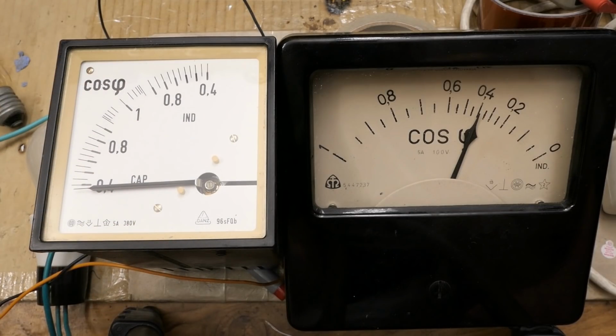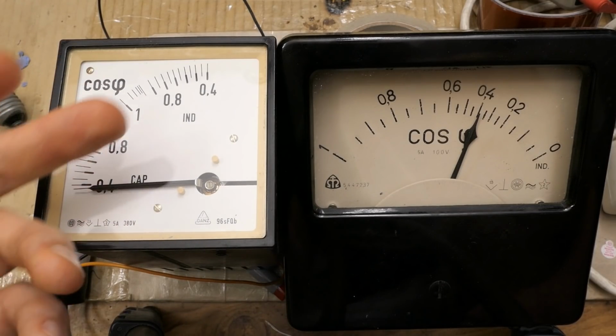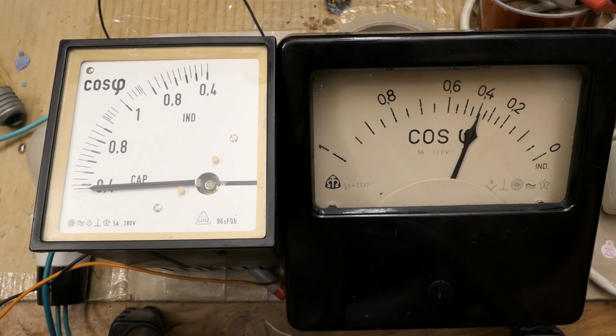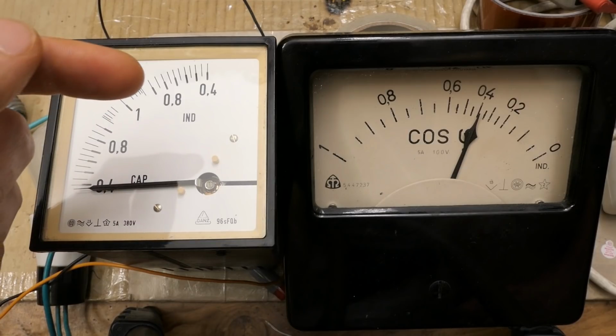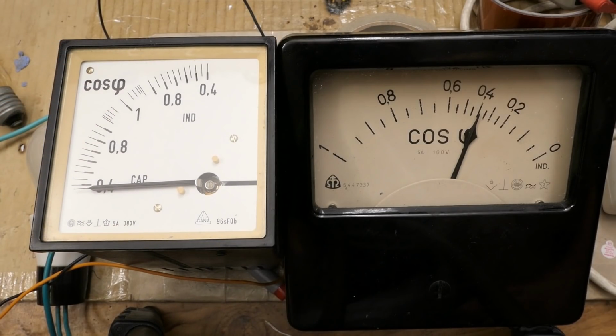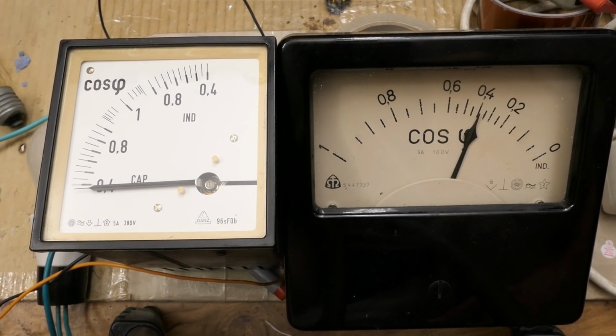But in a power factor meter there is ideally no returning force. Ideally it's just floating on perfect bearings and it's just aligning to a certain angle based on the phase angle of the voltage in the coils. In a voltmeter, current meter or a wattmeter, the connections to the coils are actually working as springs with a defined force. But in a power factor meter, the connections are not meant to work as a spring. They are meant to be as easy to move as possible.